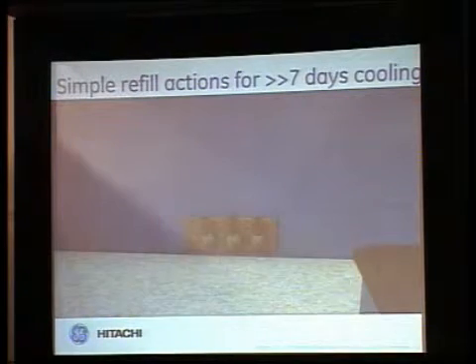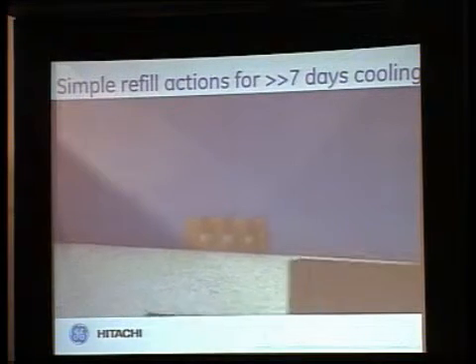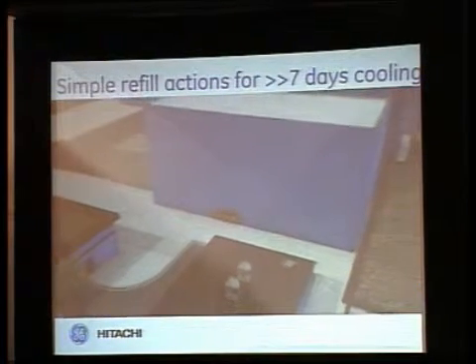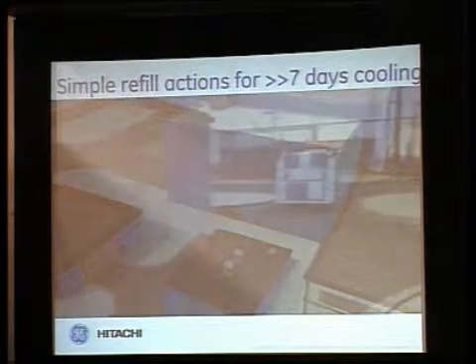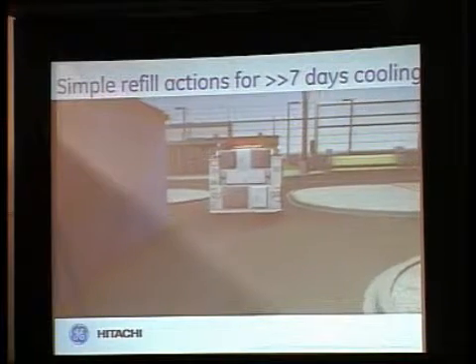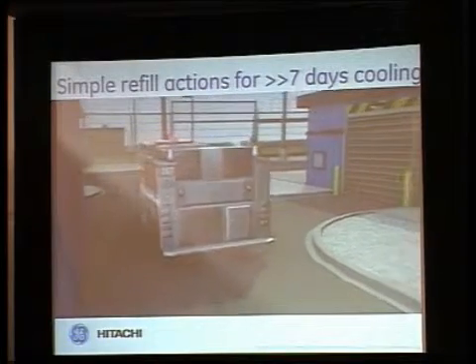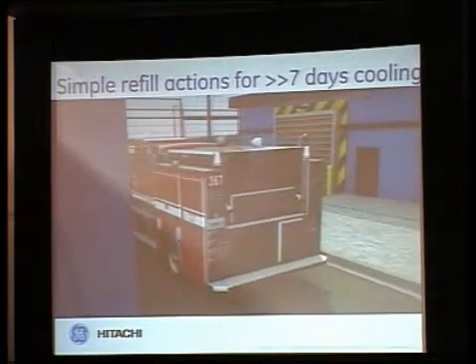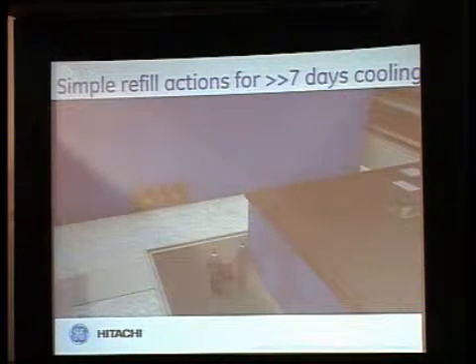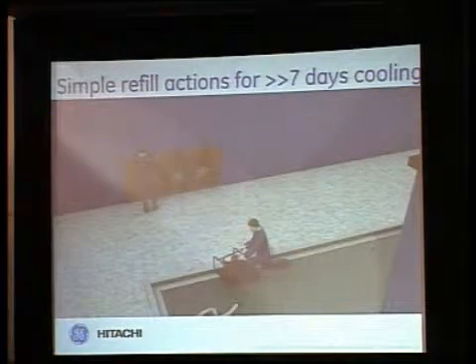If in the unlikely event the rugged diesel pump is not available, dedicated refill lines are available outside the reactor building to provide a simple but reliable means of refill. Many types of pumps can provide sufficient water for refill of the pools. Backup pump operations could include a fire truck, small hand-carried pump, or even a local farmer's tractor-powered irrigation pump. This breadth of options is the result of the pools not being under pressure and open to the atmosphere. A small hand-carried pump could be easily stored securely on site, or, if needed, could easily be transported in a small pickup truck or van.